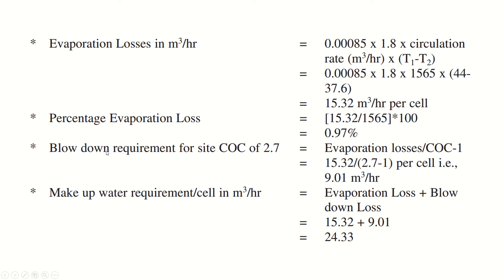For blowdown loss calculation, the cycles of concentration on site is given as 2.7. Using the formula — blowdown equals evaporation loss divided by (cycles of concentration minus one) — with evaporation loss of 15.32 and cycles of concentration of 2.7, we get blowdown loss of 9.01 m³/hr. These two losses — blowdown and evaporation — represent the amount of water wasted per hour that must be replenished.